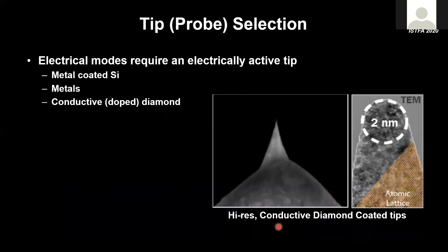The second practical aspect is probe selection. Every mode has a family of probes well suited to that particular measurement. One important example: for high-resolution electrical measurements on relatively hard samples that can wear out a sharp tip, a diamond-coated tip is ideal. It has a tip size down to a few nanometers, is made of highly doped diamond — nicely conductive for all electrical measurements — but also very robust to handle harder sample types. There are many other tip options including various metal-coated tips.